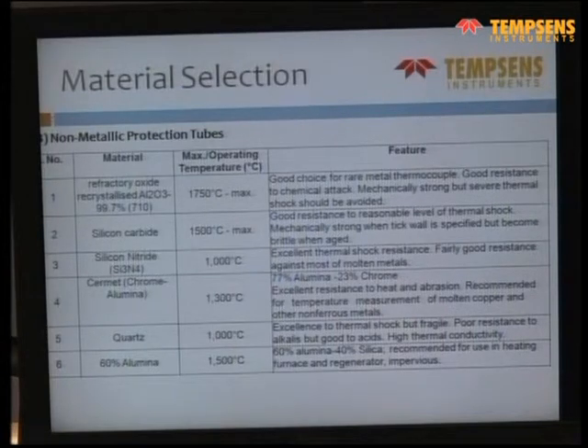As you see, the metallic tubes are mainly up to 1200 degrees centigrade or 1300 degrees centigrade. More than that, you have to go for a ceramic tube. Even at 1200 degrees centigrade, you don't have a proper metal tube which can give you a good life. So more than 1100 degrees centigrade, you have to go for ceramic tube solutions. And the most common is this C799 or 99.7% alumina tubes.